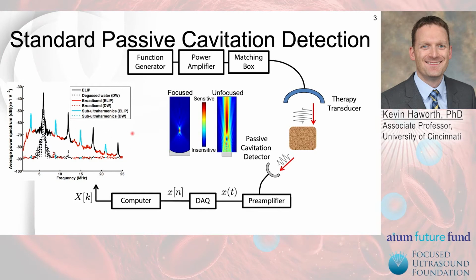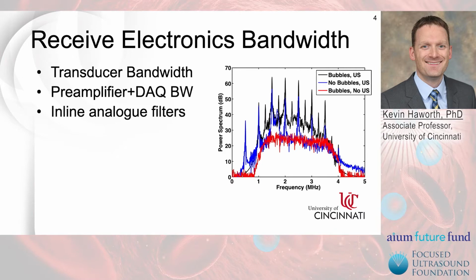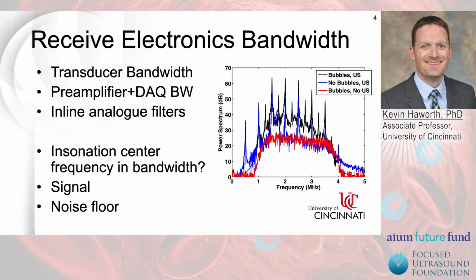Now, the choice of a passive cavitation detector can be designed to be sensitive over a relatively large area by using an unfocused transducer, or over a relatively small area with a focused transducer, and the application is the thing that dictates which of these we would select. Now, the choice of the transducer, preamplifier, and data acquisition tool should be designed with the bandwidth of interest in mind. In addition, it may be possible to use an inline analog filter to further assist in this. Now, care should be taken when determining what to use for these, in particular, whether or not we want to include the fundamental insonation frequency within that bandwidth, which can be a very large signal that can affect the signal-to-noise ratio of other frequencies that are much smaller, such as our ultraharmonics or inharmonic or broadband emissions.